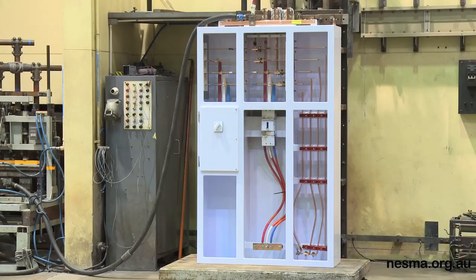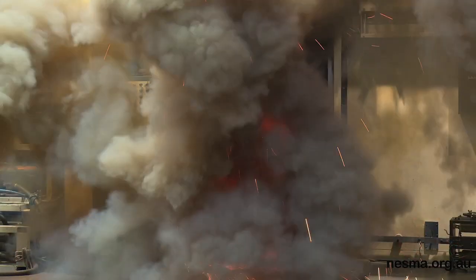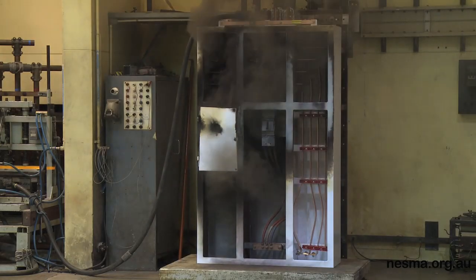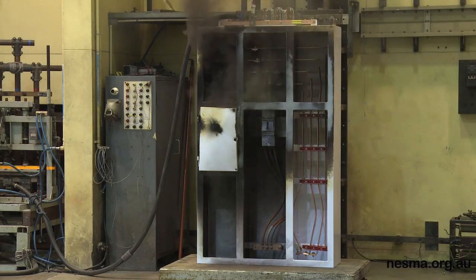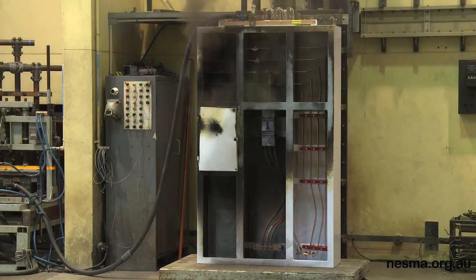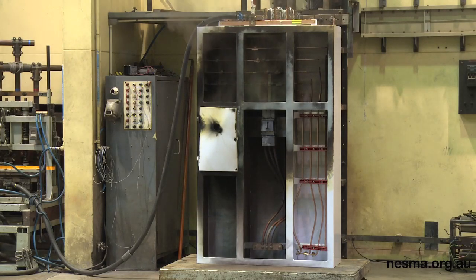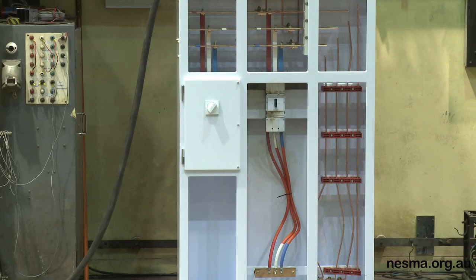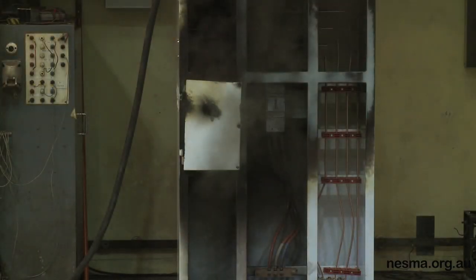However, if you were going to consider that the board was still suitable for further energisation, so we're saying that the fault had occurred in that compartment, every other compartment hasn't seen any damage or arcing generated from that fault, so that unit can be isolated, and then the assembly passes a dielectric test and can be deemed fit for emergency or further service until an appropriate remedial time can be scheduled to repair the assembly.